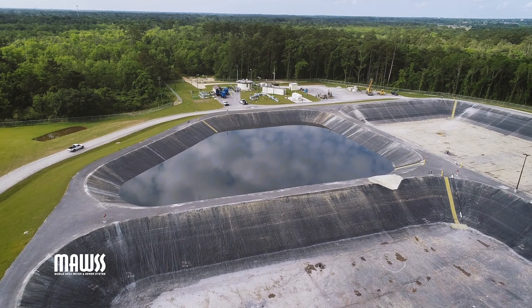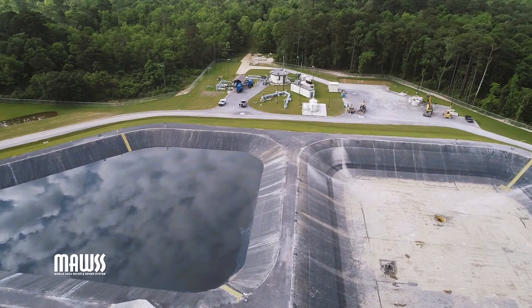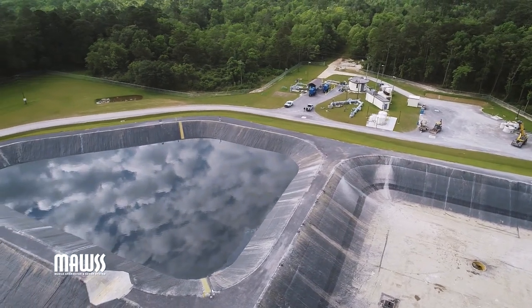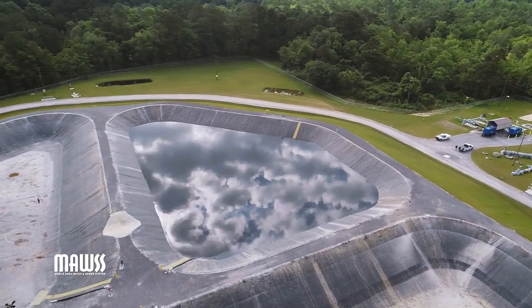We just recently constructed a SWAB facility at our Halls Mill Basin. Our system is divided into three basins. We have our Three Mile Basin, our Eslava Basin, and our Halls Mill Basin. And in this basin, we constructed SWABs, which are open basins, to divert the amount of water we're not able to maintain in our system. It's like a bottleneck. As we get too much water in, we can't maintain it and can't pump it. So we built these basins that we divert this rainwater into automatically. It's a great system. It's signaled by levels, and as the levels get up, an automatic valve will divert the flows into these basins, and it will hold them there until we're able to pump the capacity we need. Another investment that we're looking to make to reduce SSOs.